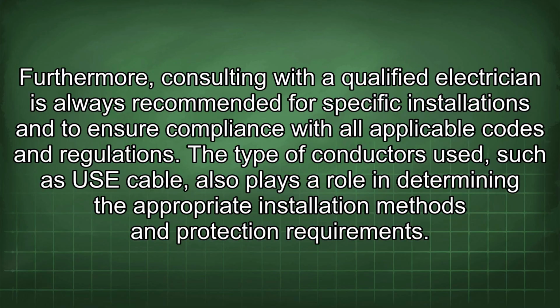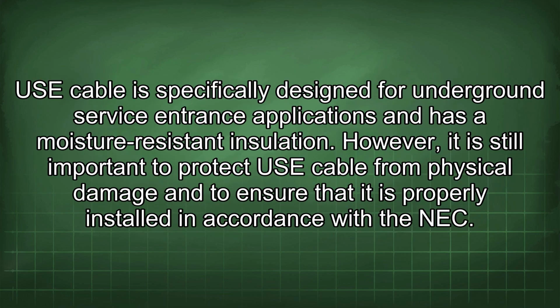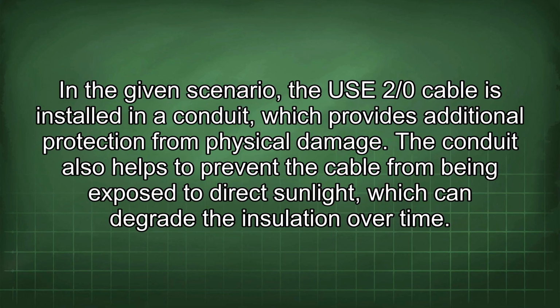The type of conductors used, such as USE cable, also plays a role in determining the appropriate installation methods and protection requirements. USE cable is specifically designed for underground service entrance applications and has a moisture-resistant insulation. However, it is still important to protect USE cable from physical damage and to ensure that it is properly installed in accordance with the NEC. In the given scenario, the USE 2/0 cable is installed in a conduit which provides additional protection from physical damage. The conduit also helps to prevent the cable from being exposed to direct sunlight, which can degrade the insulation over time.